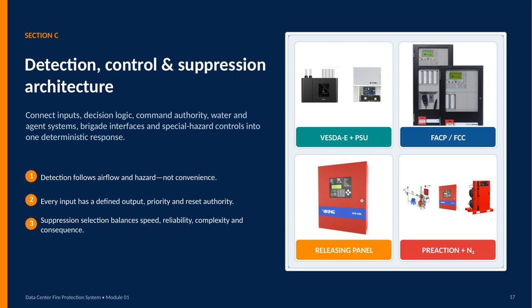There are 3 principles to keep in mind. First, detection should follow airflow and the actual hazard, rather than simply reflecting what is easiest to install. Second, every input needs a defined output, priority, and reset authority. That clarity helps prevent ambiguity when multiple signals arrive or when the system needs to be restored. Third, suppression selection has to balance speed and reliability with complexity and consequence. The fastest option is not automatically the best option if it introduces unnecessary risk or operational burden.